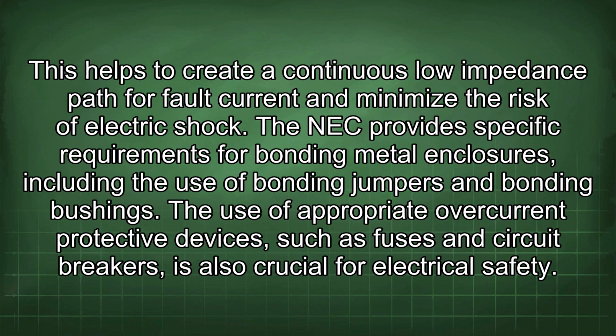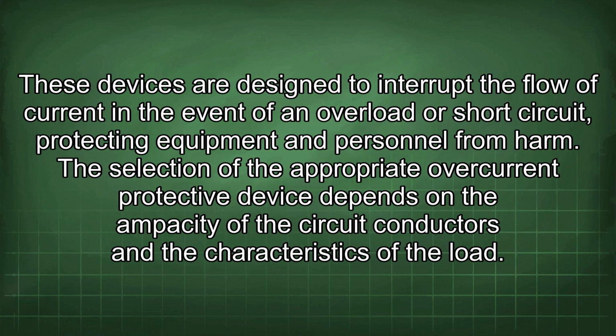This helps to create a continuous low impedance path for fault current and minimize the risk of electric shock. The NEC provides specific requirements for bonding metal enclosures, including the use of bonding jumpers and bonding bushings. The use of appropriate overcurrent protective devices, such as fuses and circuit breakers, is also crucial for electrical safety.